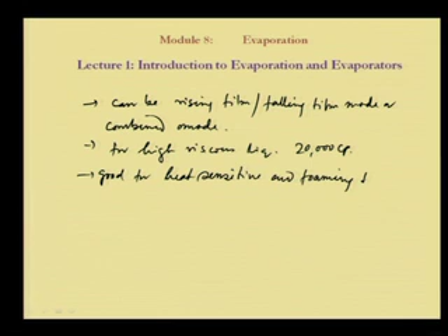Then another one is the plate type evaporator, which is similar to the plate type heat exchanger. Here also it can be rising film, falling film, or a combined mode. It can be used for highly viscous liquid of, say, 20,000 cP viscosity. This is also good for heat sensitive and foaming solutions. In the plate type heat exchanger, on one side there will be steam, and on the other side there will be the liquid to be heated. This is the plate type heat exchanger that is being used.